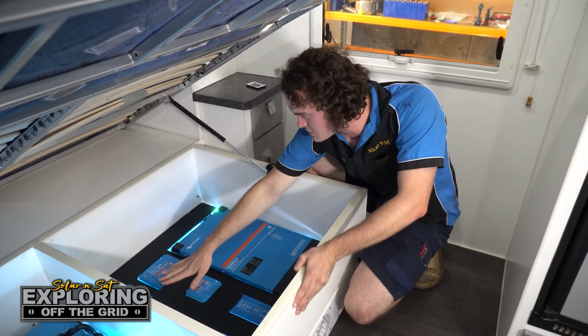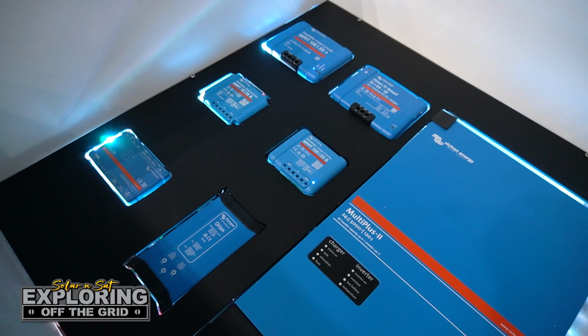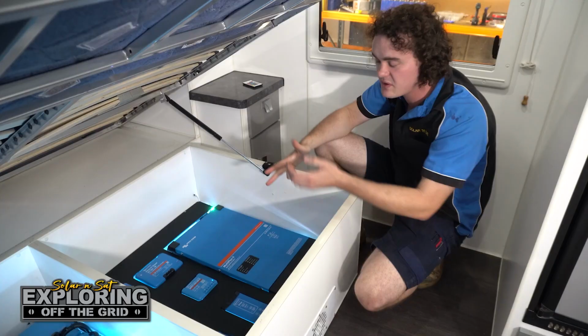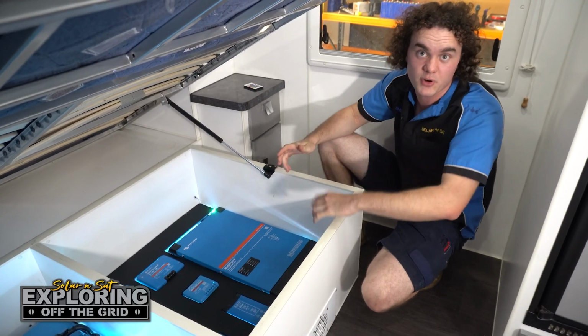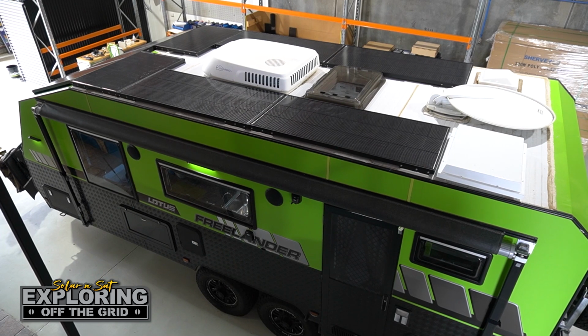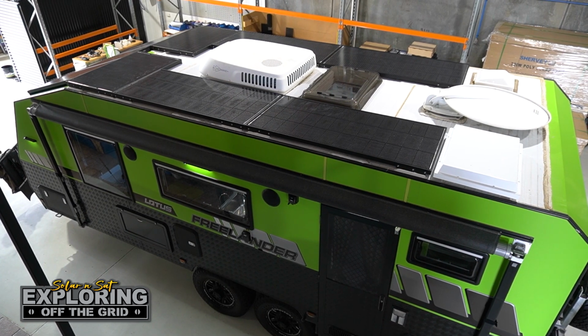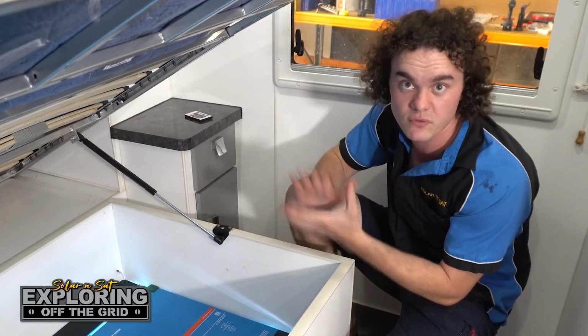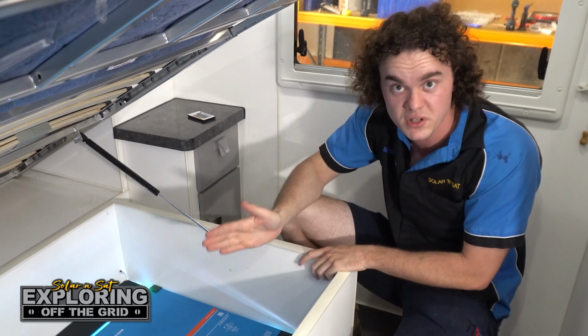Then we've got 3 solar controllers - the 100-50, the 75-15, and the 100-20, all from Victron. The big fella there is for that massive solar array we've put on the roof, the flat mounted stuff all run through that unit. You can take twice as much now that it's wired up for 24 volt - typically they're good for 700 watts, but in this case it's actually good for 1400 watts.